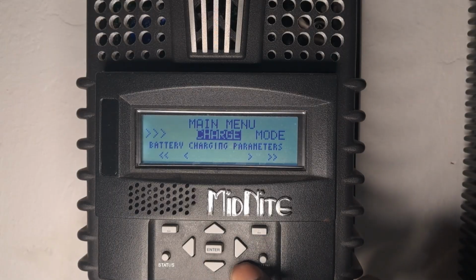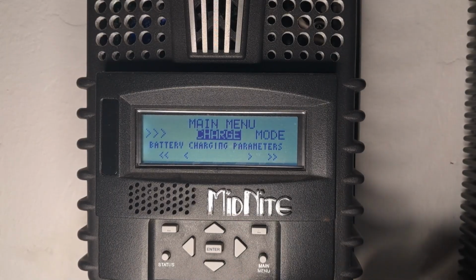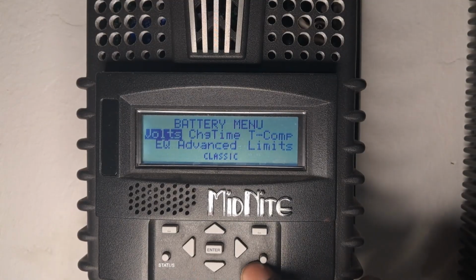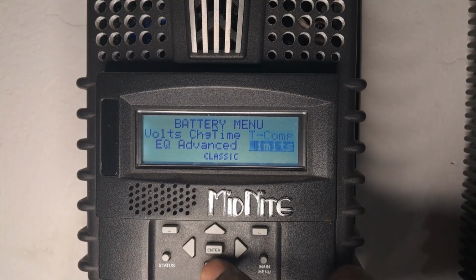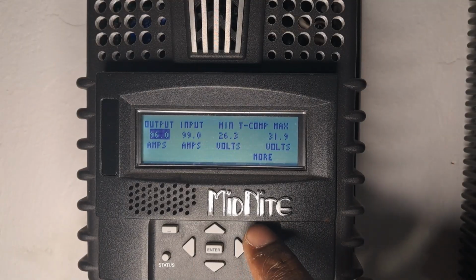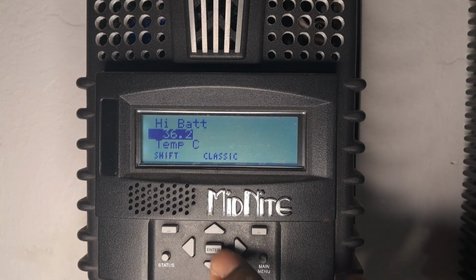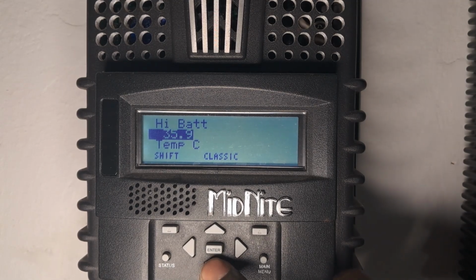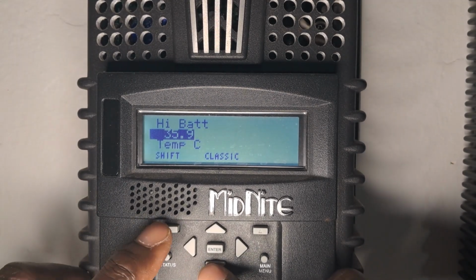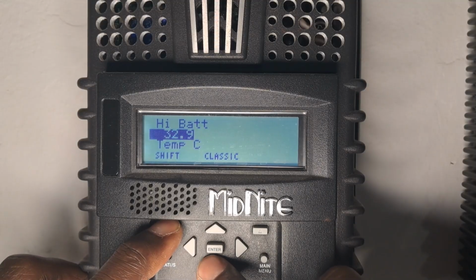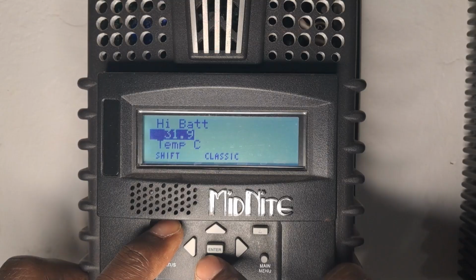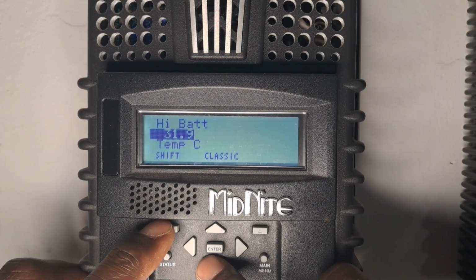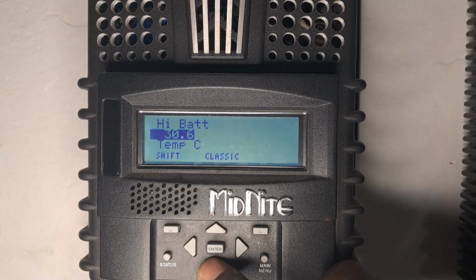Whenever you go into the main menu, if you're not on charge, press main menu a couple of times to get to the charge menu, then enter on charge. Remember the temperature setting is under charge. Go to limits, enter, then more, and we can go down from here. To change the whole number, press shift and go down. We're going down to 29 or 28, anything under what's there now.